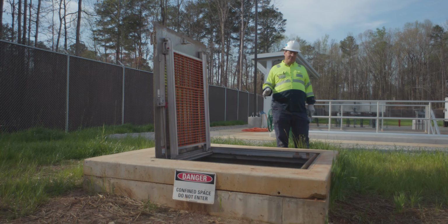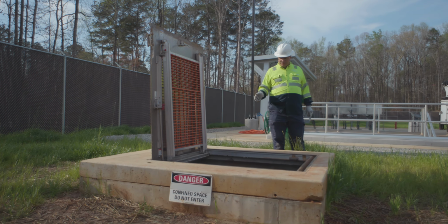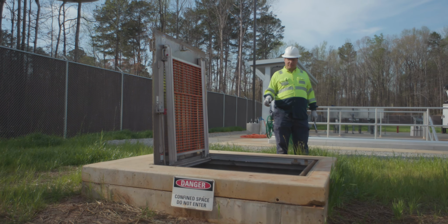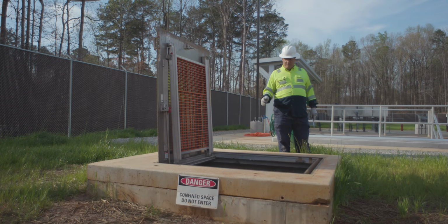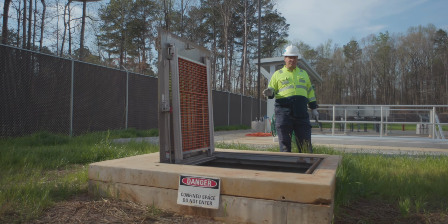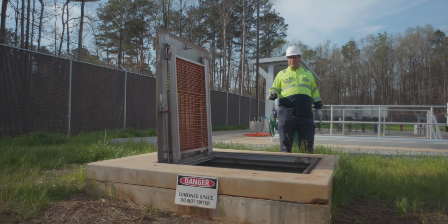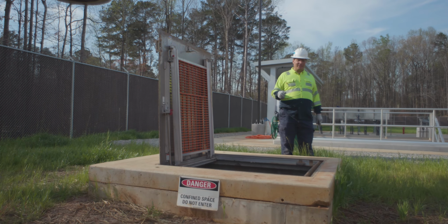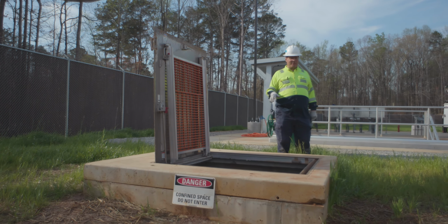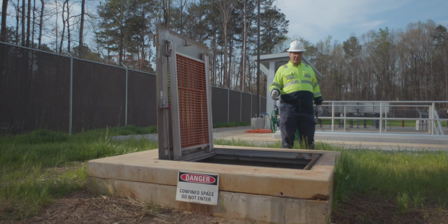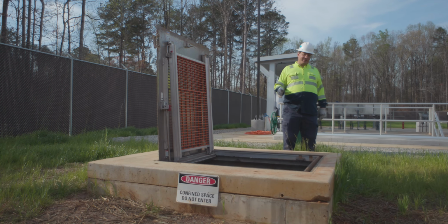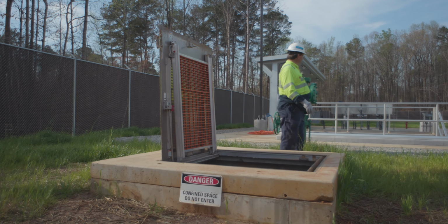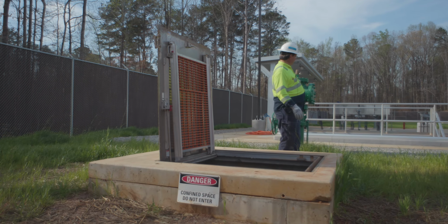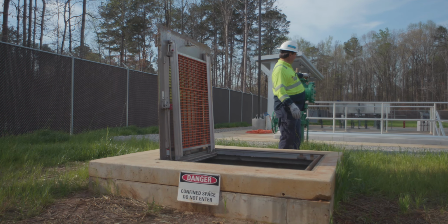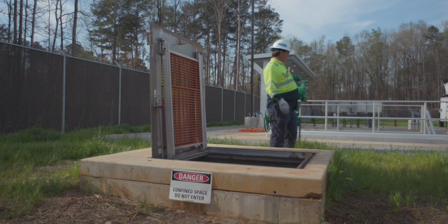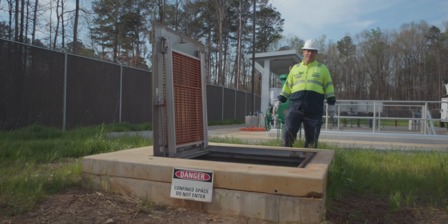We're on the force main after it leaves the valve vault, and in this vault there's a pressure transmitter and a flow meter. From here we're taking 4 to 20 signals, and we're reading the pressure in the force main, which is going to be a little bit less than the pressure that the pumps see because the pumps are lower than this pipe. So when they look at the pressure on the force main, it's not the discharge pressure of the pumps. The discharge pressure of the pumps includes all the resistance going through these pipes, plus the check valves and the plug valve, and the distance down and the head elevation difference going down to the pump.